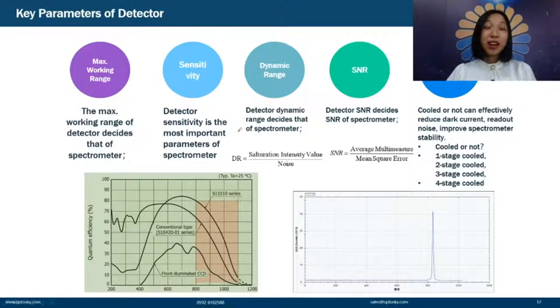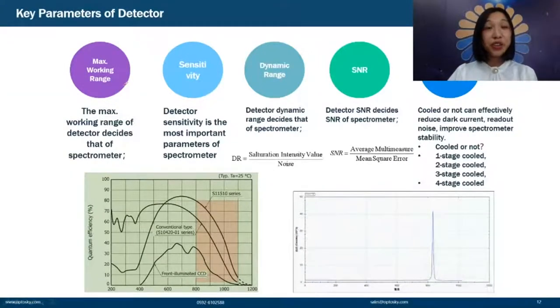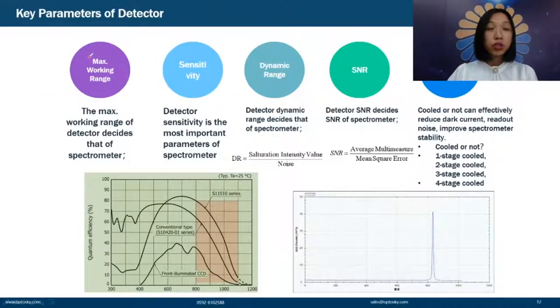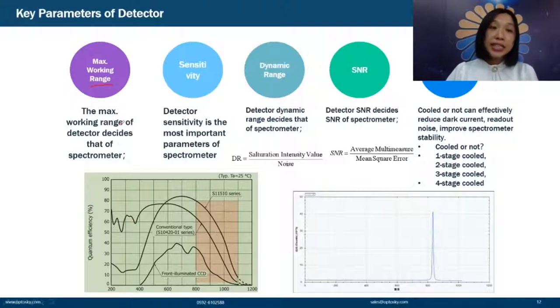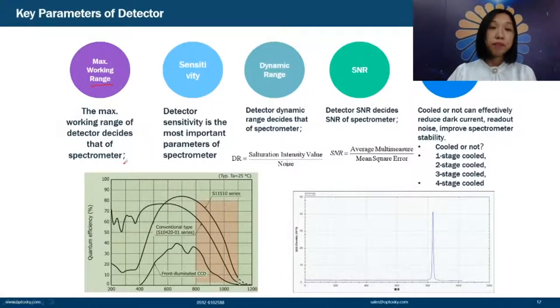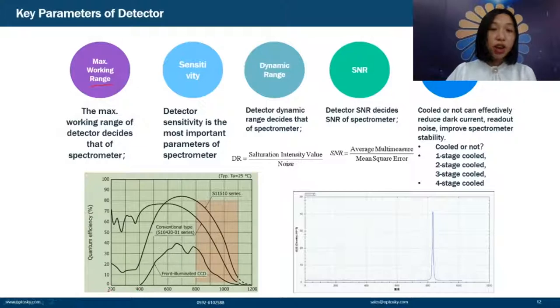After introducing the detector principle, let's look at the core detector parameters. First is the maximum working wavelength range — by selecting the appropriate detector, its working range decides the spectrometer's wavelength coverage. For example, Hamamatsu detectors can cover from 200 to 1150 nm.